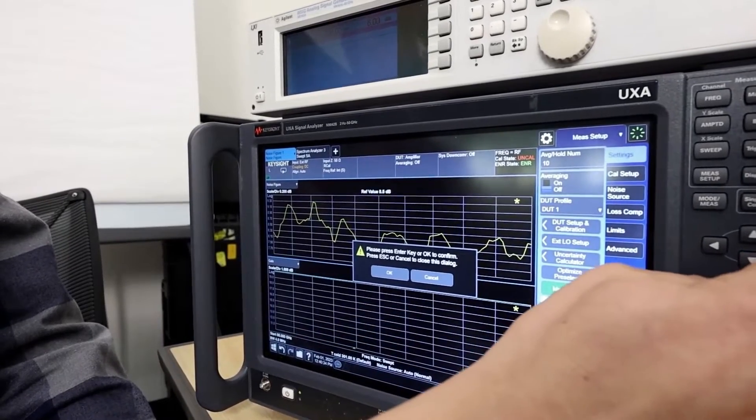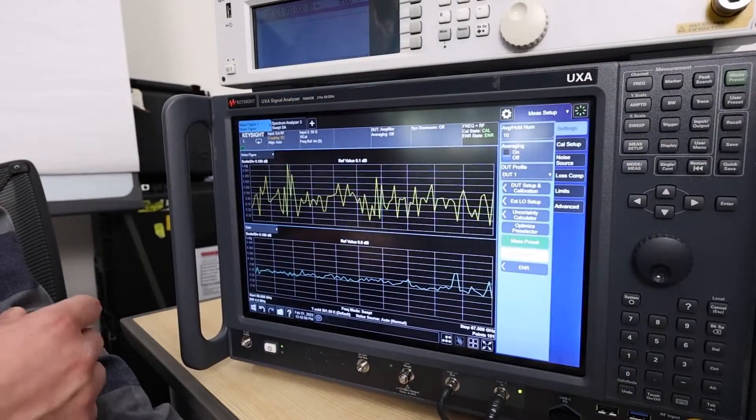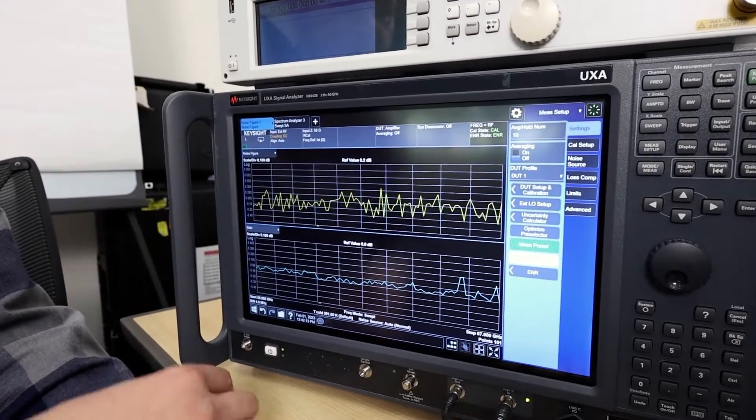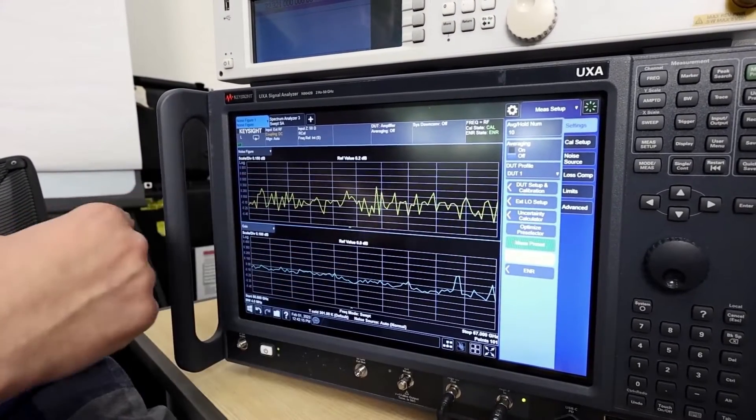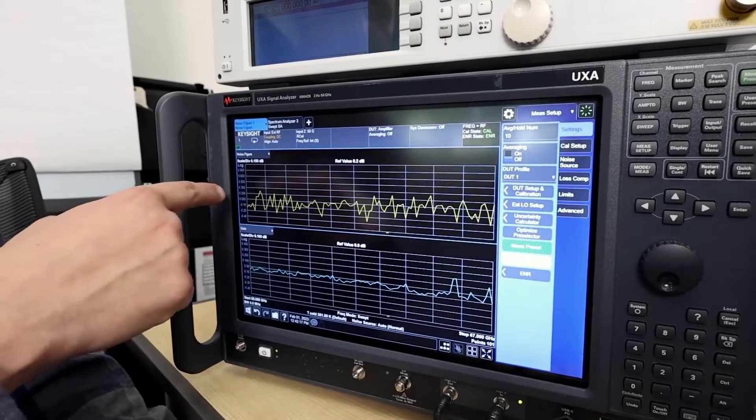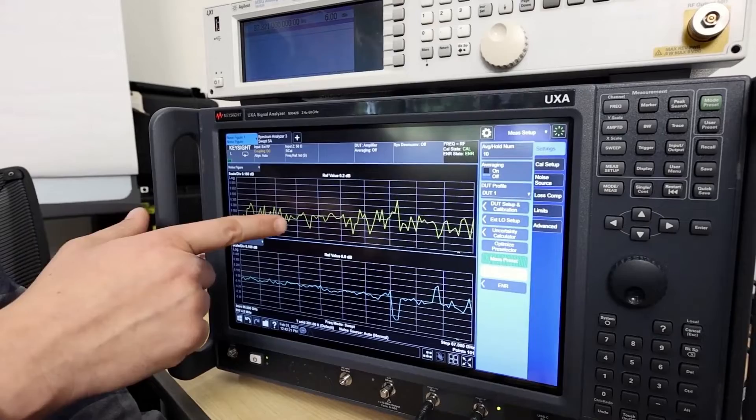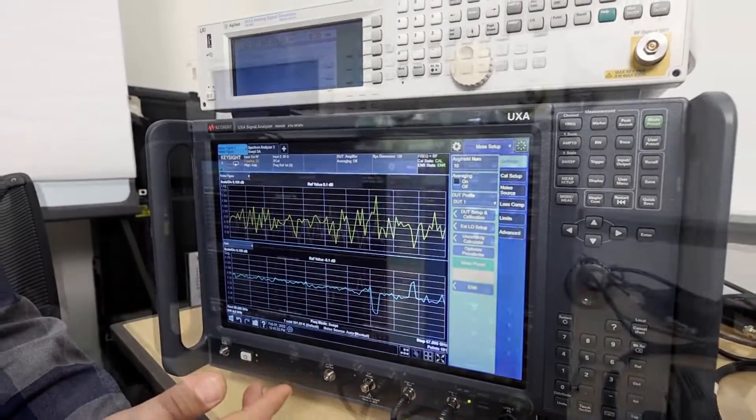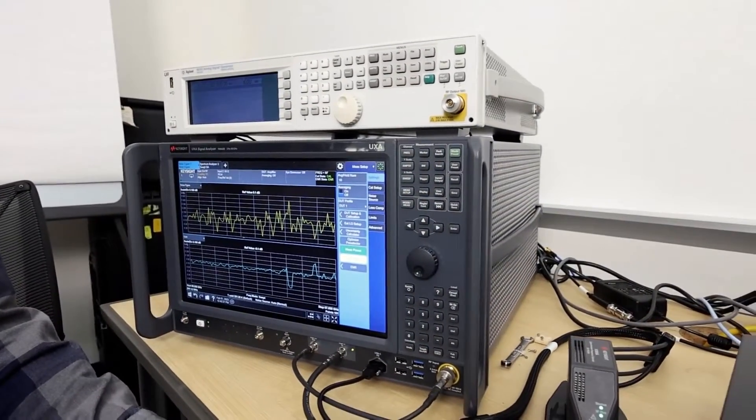So I'll go ahead and calibrate. Now we've calibrated. We have the auto coupled scale. So we see around zero dB for our noise figure and zero dB for the gain, which is what you would expect for a good calibration.